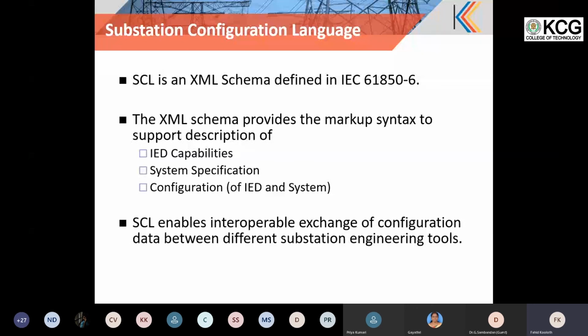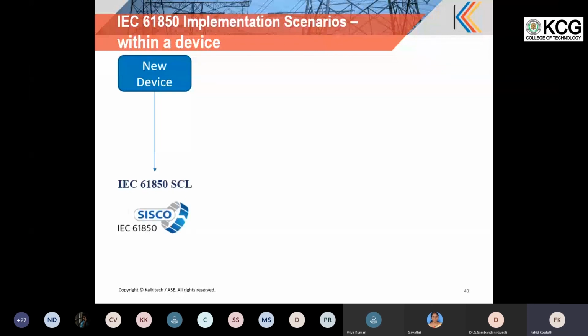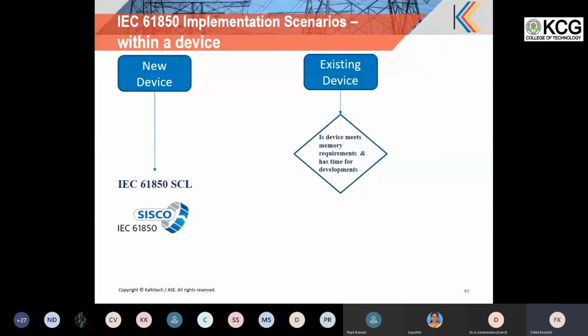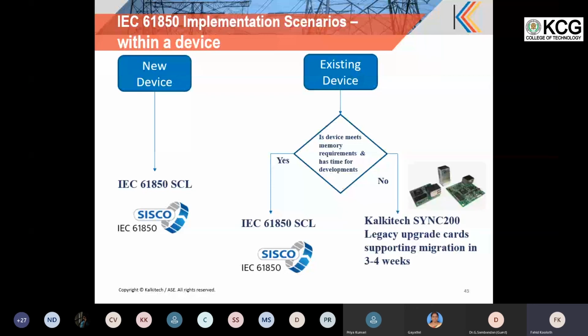Then moving on to some of the implementation scenarios. For a new device, a 61850 source code library is available, so you can migrate directly into a new device. For an existing device, if you want to migrate, it needs to meet the memory requirement and there must be time for development; then you can switch. In a similar scenario, the SCL source code library can be used and migrated. If the time is not suitable, then OEM modules like a legacy upgrade card can be used for integration. So this is the device level migration that can be adopted.